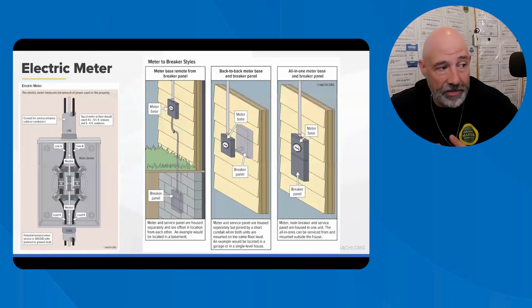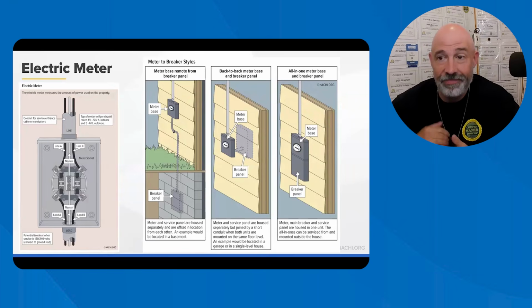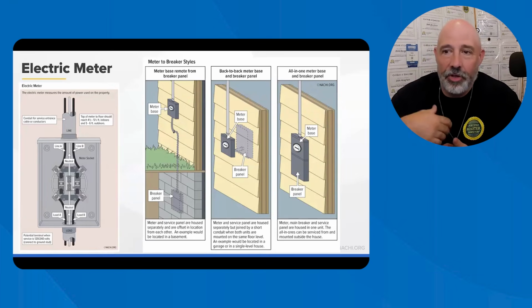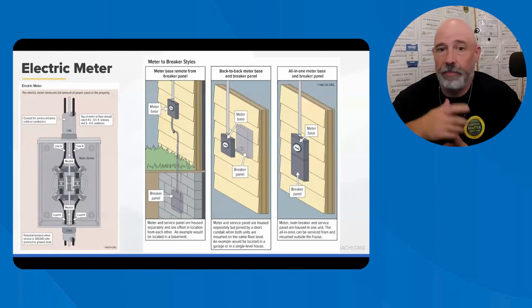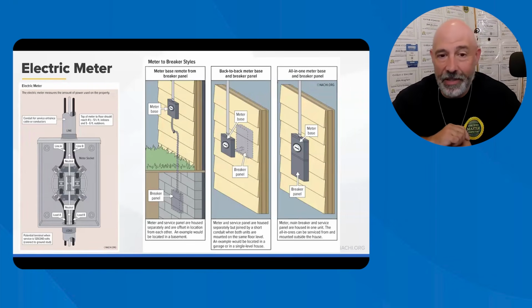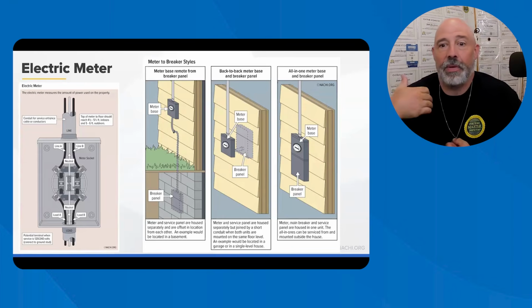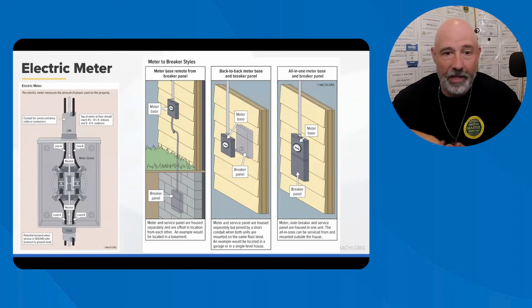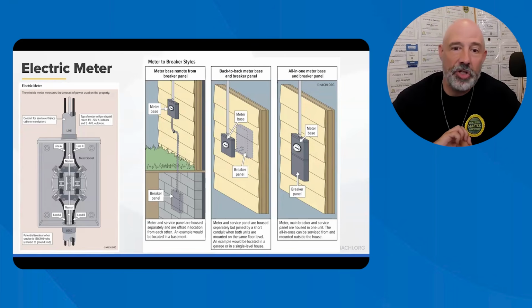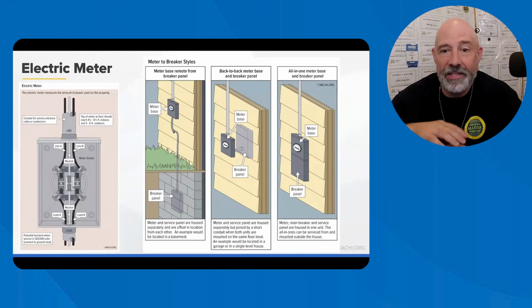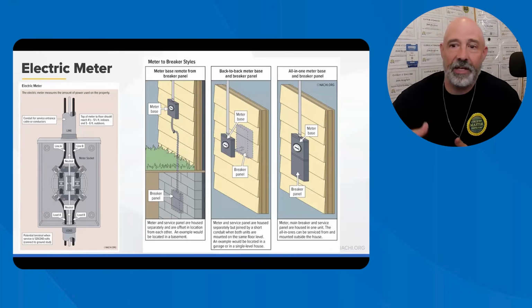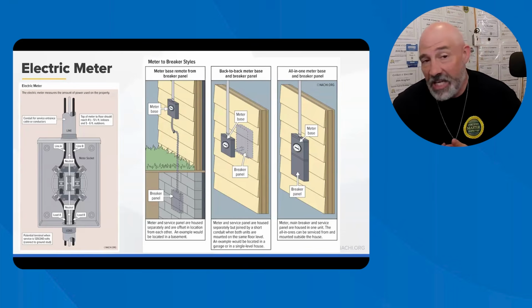Electrical meters and meter bases. The electrical meter measures the amount of electricity used by the property and is not considered part of the service equipment. The meter base is the enclosure where the utility installs the meter. Depending on the house design, the main disconnect may be located in the main panel at the meter base or in an exterior disconnect enclosure. When the main disconnect is separated from the panel, the conductors running to the panel are called feeders.